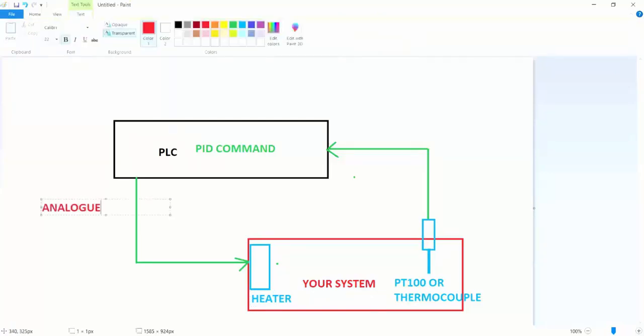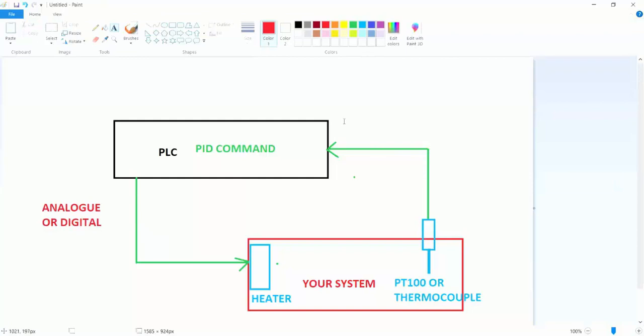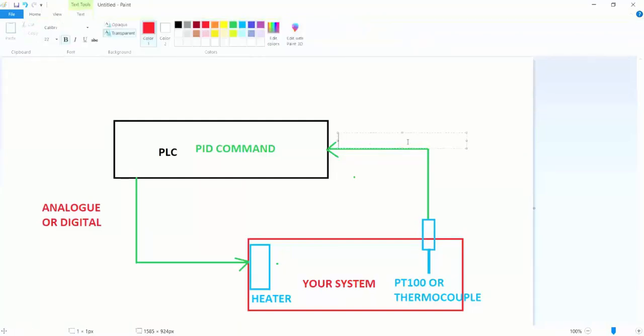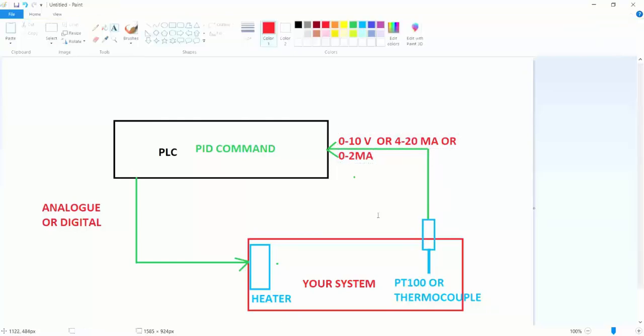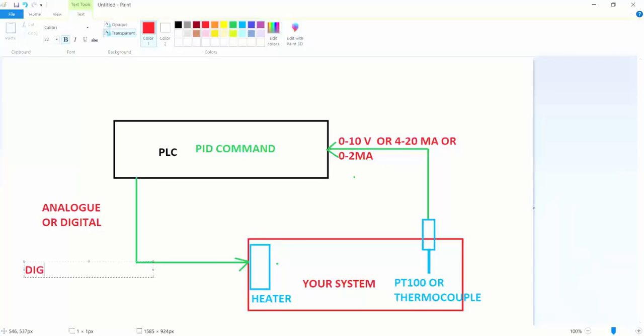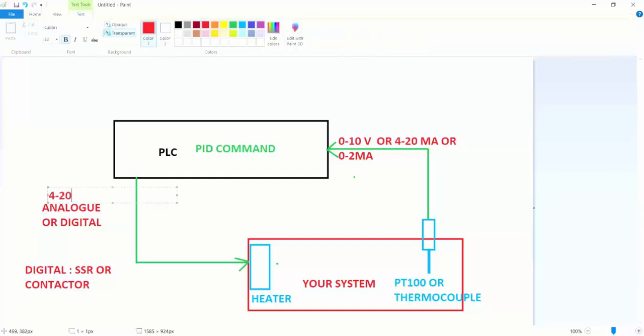This output can be analog or digital. You also get information from a sensor — the sensor must be analog, for example 0 to 10 volt, or 4 to 20 milliampere, or 0 to 20 milliampere, etc. You get information from the sensor this way and control the system with the output — analog or digital. For example, digital can be SSR or a contactor, and analog may be 4 to 20 milliampere or 0 to 10 volt.